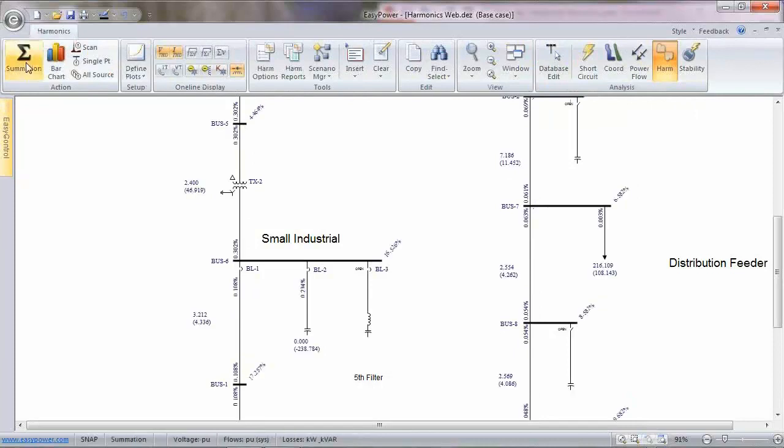Harmonics, with the resonance, we're at 2.4. Without it, we're 1.7. So under this standard condition here, without any resonance or filtering going on, you find basically that the harmonic losses are kind of a small portion here. And that's what I was trying to get to, that I was telling you earlier. Even under heavily distorted conditions.